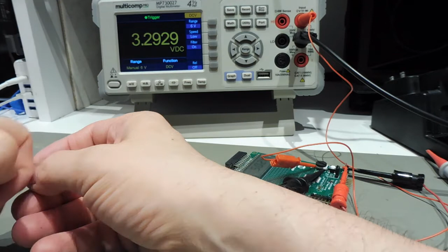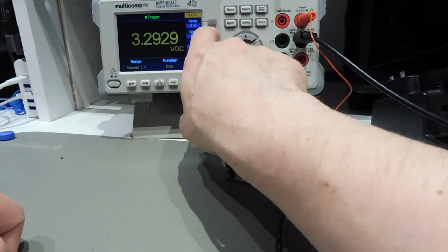For a bench multimeter like this one, you might have additional functionality. One is called measurement speed, so you can switch between low, medium and high measurement frequency. For this one it doesn't change that much, but for many meters, changing the speed setting changes the specification of how accurate it is, and sometimes even how many digits you get. So for a 7-digit multimeter, you might only get that on the lower speed, and when you switch to a higher speed you only get 6 or 5 digits, because the higher speed reading reduces accuracy.